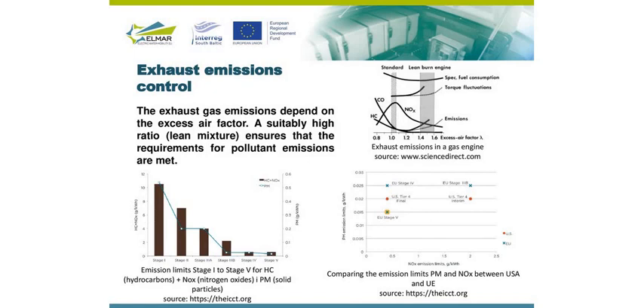Reciprocating engines need to meet gas emission limits, and the emission can be controlled by a suitable high ratio lean mixture, which is the factor which ensures that the requirements for pollutant emission are met. We can see in this diagram the requirements for different stages, and the emission limits are much smaller for the last stage required by the European Union compared to the previous stages.